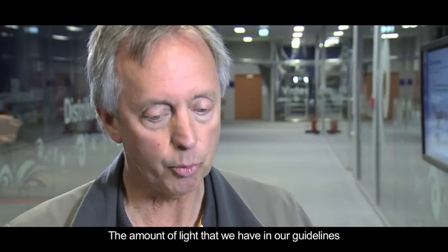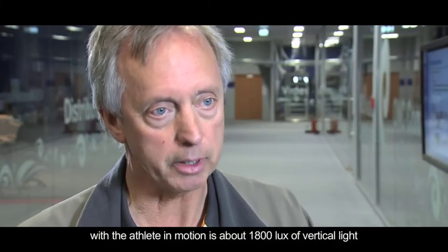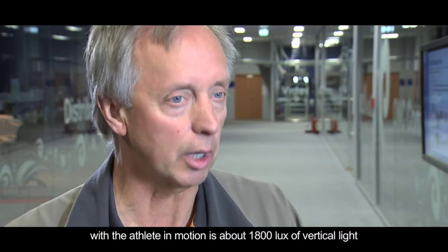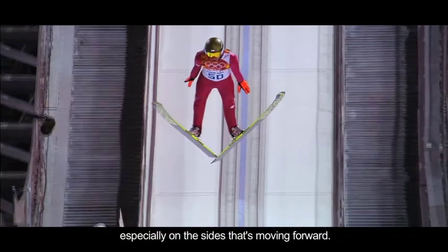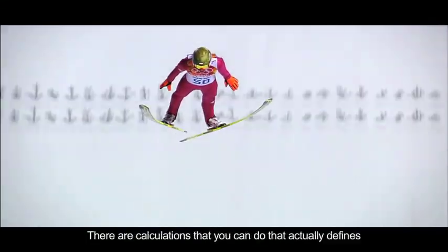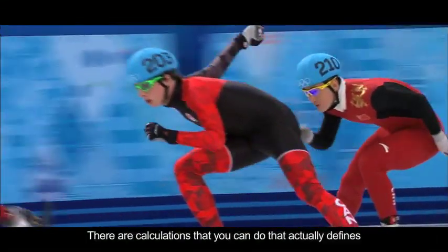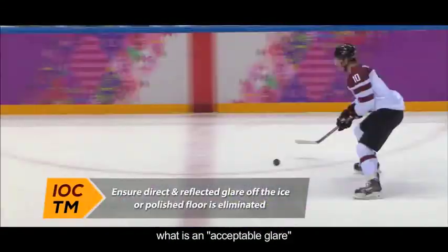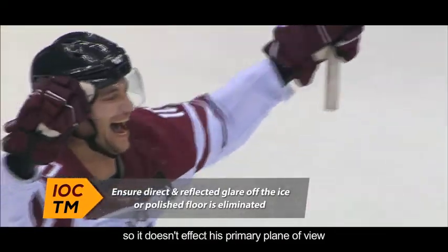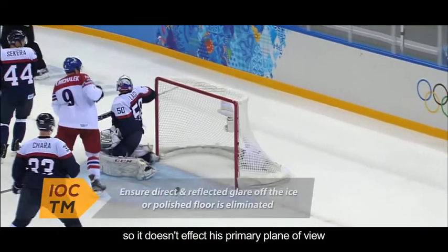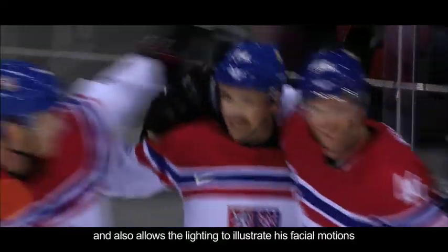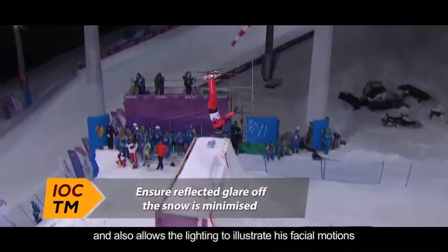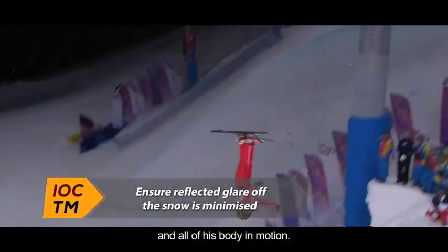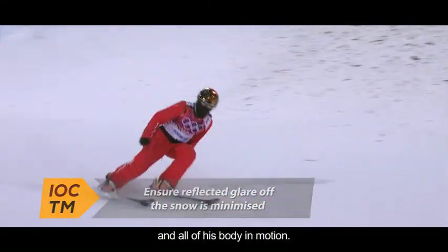The amount of light that we have in our guidelines with the athlete in motion is about 1800 lux of vertical light on the athlete on all sides of him, especially on the sides that are moving forward. There are calculations that you can do that actually define what is acceptable glare, so it doesn't affect his primary plane of view, and it also allows the lighting to illustrate his facial motions and really all of his body in motion.